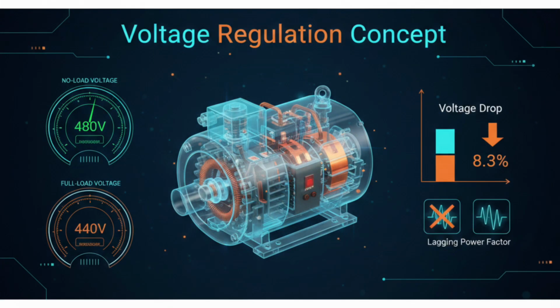Voltage regulation concept. Now let us start with the concept of voltage regulation. On this slide you can see two meters, one showing no load voltage and the other showing full load voltage. When an alternator is running without any electrical load, the terminal voltage is usually slightly higher. As we connect loads and current starts flowing in the stator windings, internal voltage drops appear, causing the terminal voltage to reduce. Voltage regulation is expressed as a percentage and is calculated by taking the difference between no load voltage and full load voltage, dividing that by the full load voltage, and multiplying by 100.